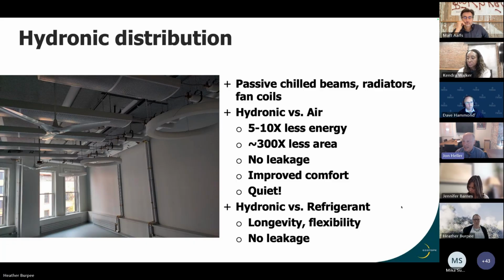This provides for the maximal energy efficiency. Pumps are way more efficient than fans or compressors to push heat around a building, 5 to 10 times less distribution energy. Resilience: the distribution system in the building is really agnostic to what's creating the hot or cold water. So the heat pumps can be changed out in the future on the roof without any impact to the internal distribution, which is not the case if you were using a VRF system, for example. The refrigerant piping is likely going to have to be changed if and when the heat pumps are changed outdoors. Hydronic is also a lot easier to reconfigure the building than if you've got a big ducted system and want to change that around.